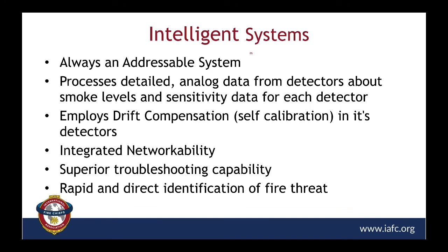What makes it intelligent? Not only is it still addressable, but now we're taking those smoke detectors specifically and we're able to digest data coming from them by communicating with that device back to the control panel, going back and forth. We can determine whether that detector is getting dirty or getting close to going into a false alarm. As some of you may know, there's a code requirement that all smoke detectors need to be tested and inspected every year. Along with that, there are requirements for sensitivity testing of all smoke detectors. An addressable system can do the sensitivity testing for the entire building's detectors right from the control panel.